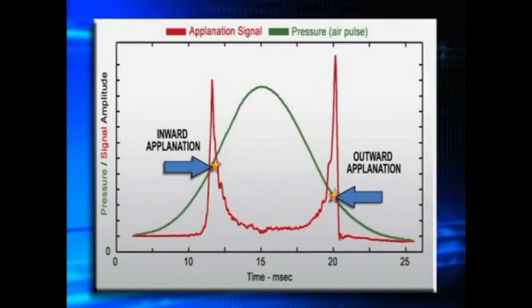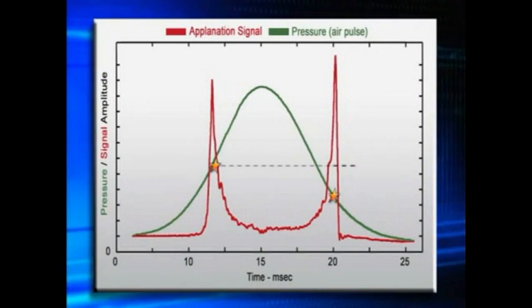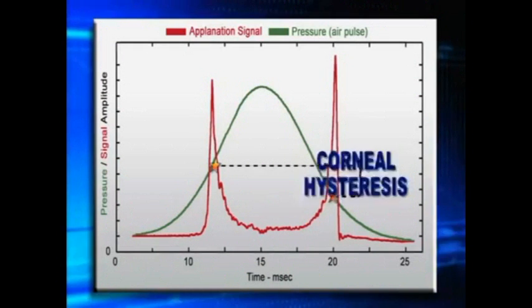One might expect that the pressure measured at the inward and outward applanation events would be the same. However, due to its viscous nature, the cornea resists the dynamic force of the air puff, resulting in a damping effect that manifests itself as a discrepancy between the applanation pressures. We refer to this phenomenon as corneal hysteresis.